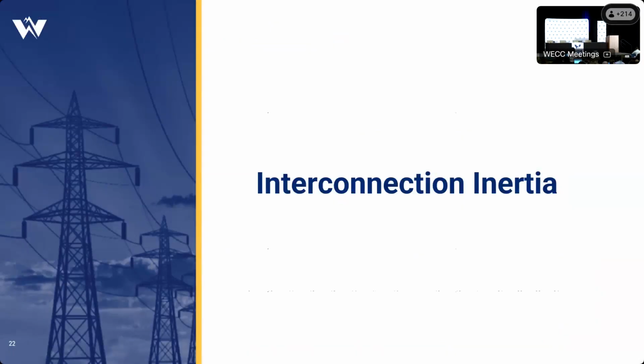ERCOT has set a minimum inertia level in the Texas interconnection. They make sure they always have a certain amount of megawatt-seconds of inertia on their system. They've done that because they have such a large penetration of wind that they had to understand their minimum inertia level. We've never done that in the West. All of our studies really show we don't have an inertia problem, and I don't think we have an inertia problem in the interconnection. But there have been some EPRI studies done in the last couple of years that show we might have some regional inertia problems.